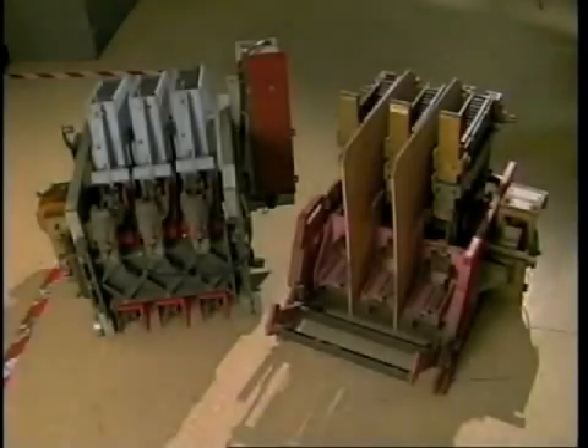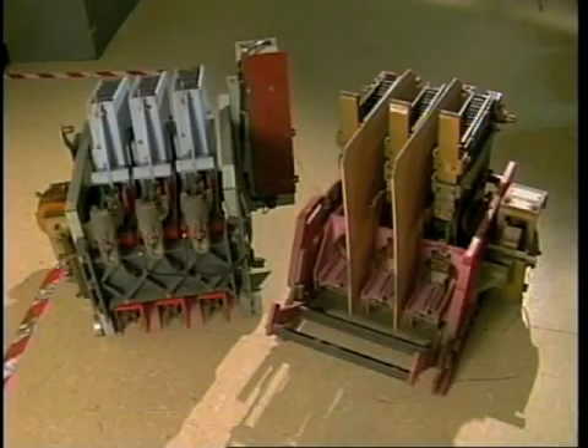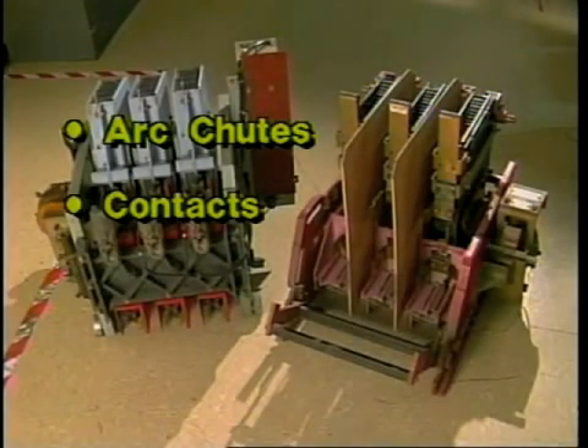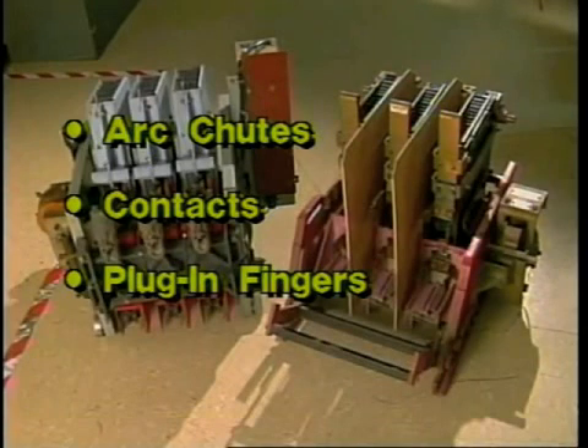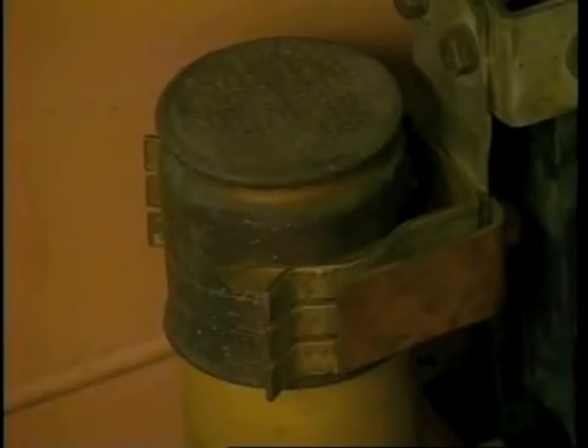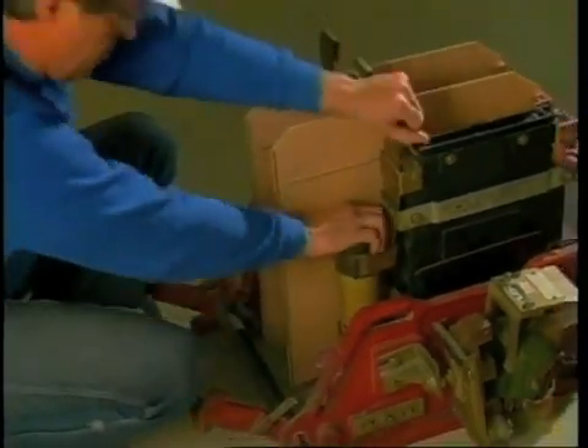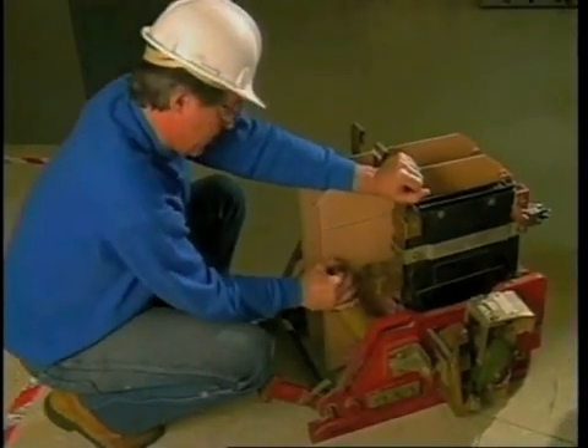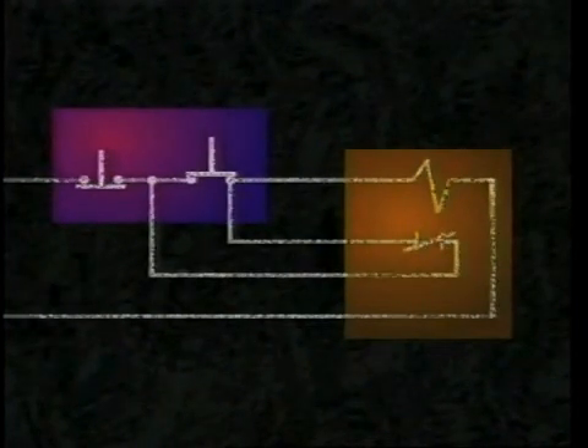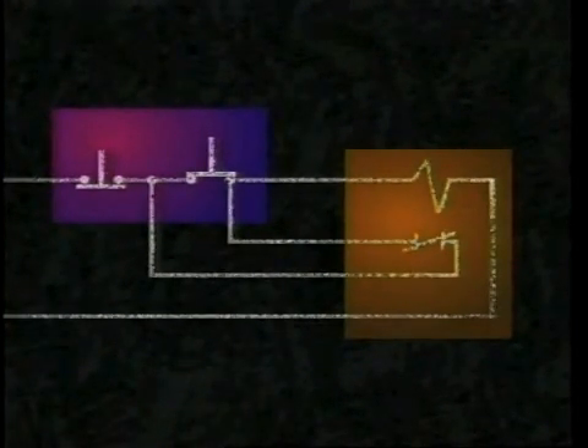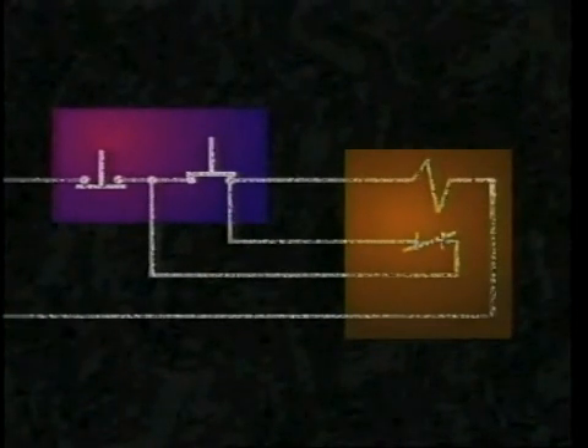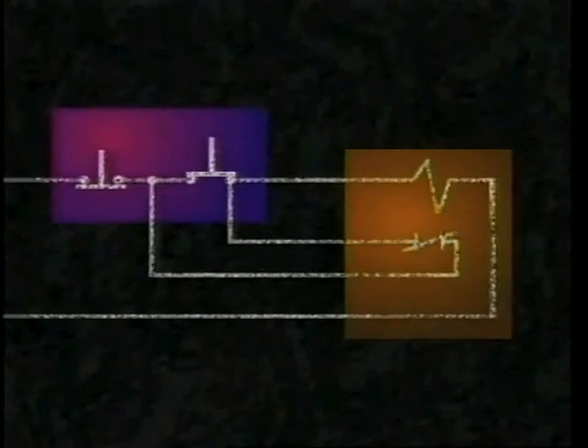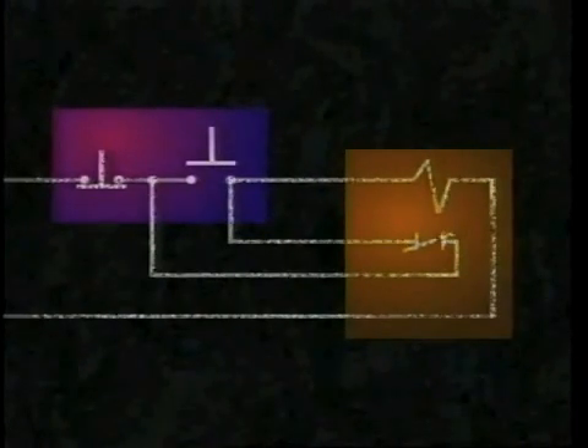Contactors have many of the same design characteristics of circuit breakers, such as arc chutes, contacts, and plug-in fingers. However, contactors are not designed to interrupt heavy fault currents. Instead, fuses are used to protect the system from damage when fault conditions occur. Contactors are closed by manual operation of a remote control device, which energizes a coil. Once closed, they're held closed by this coil. Should a loss of power occur, the coil will release the contactor to the open position.